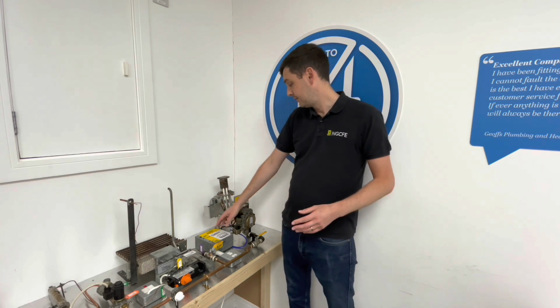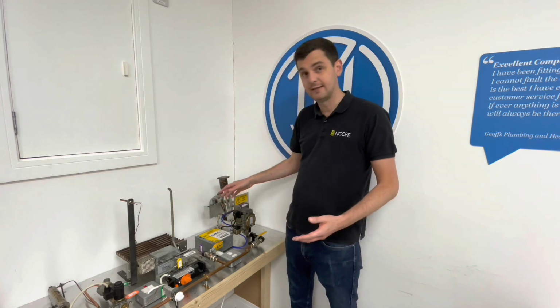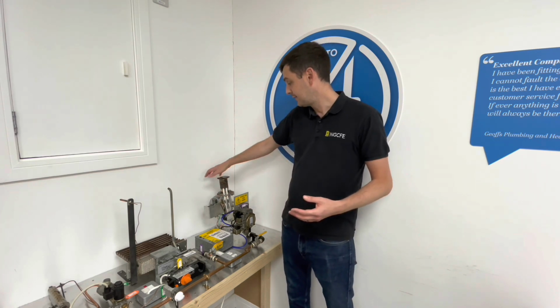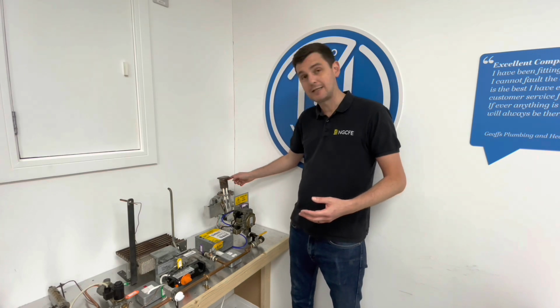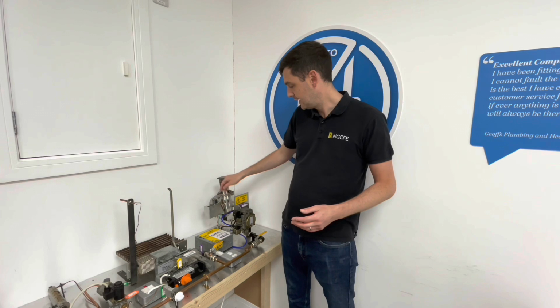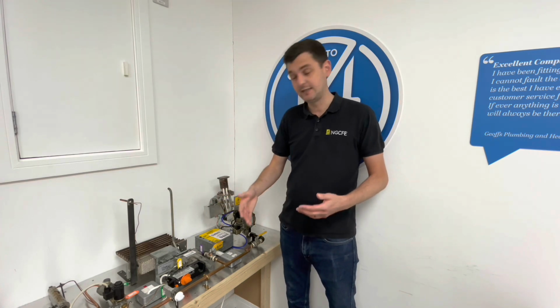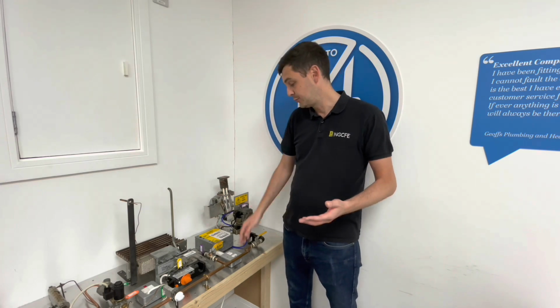So when the board sends power to the fan and the gas valve and the ignition probes to create a flame, once that flame's present, the voltage that's on the rectification probe then travels through the flame, and in going through the flame it converts from AC to DC current. It travels back via an earth or a ground lead, and once it gets back to the board as DC current, the board knows that there's a flame there. So it happens pretty instantly.